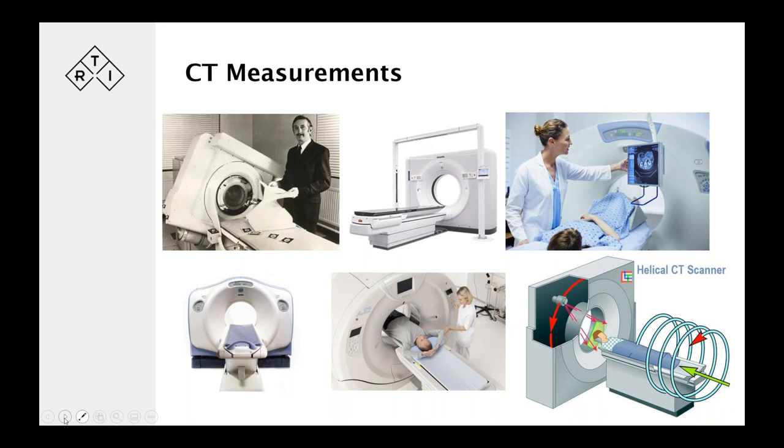There's one exception, or a couple of exceptions. For the CTs with the wider beams up to 160 millimeters, the couch will not move for collimations larger than normally 80 millimeters, something like that. Probably, I guess, because table speed would be too high if you have a pitch around 1 or something like that. So for collimations above 80 millimeters, the table is typically stationary.